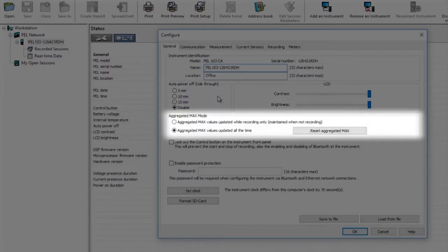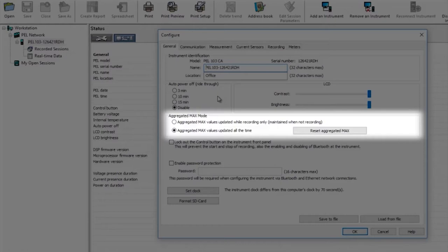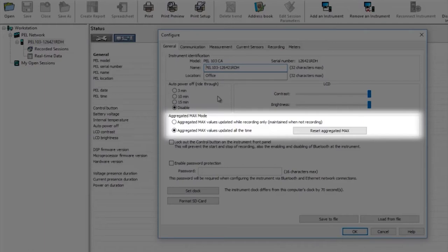AGGREGATED MAX mode is the next option. On the PEL 103 there's an icon on the front screen which when selected shows the maximum recorded values for the installation that the PEL is connected to. There are two options for this. If AGGREGATED MAX VALUES UPDATED WHILE RECORDING ONLY is selected then during a recording session you can look at what the maximum values have been for any of the recorded parameters, for example current, voltage etc. But this is only during the recorded period.